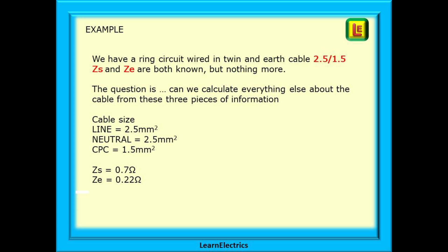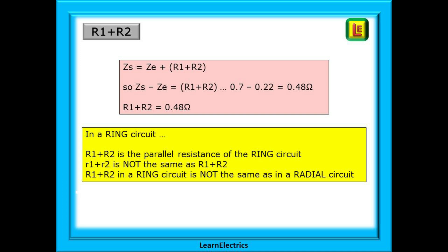The cable size, the Zs and the Ze. We should know that Zs is Ze plus R1 plus R2. And we can rearrange these to get just R1 plus R2. So Zs minus Ze will give us R1 plus R2.